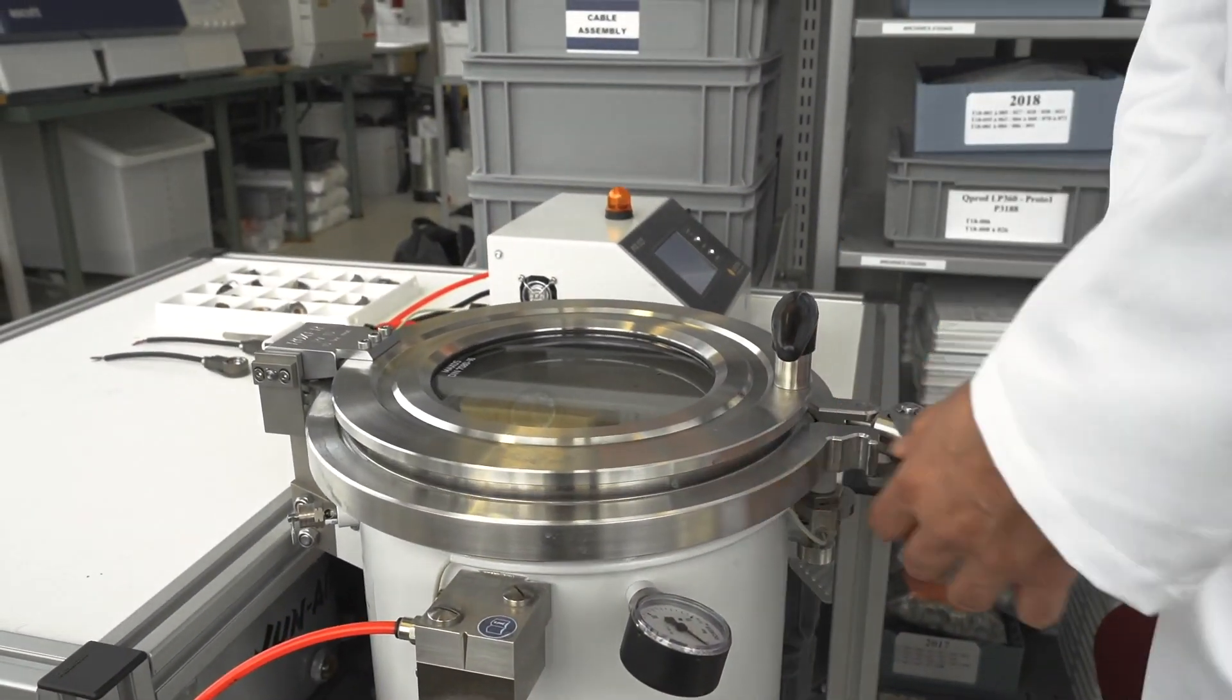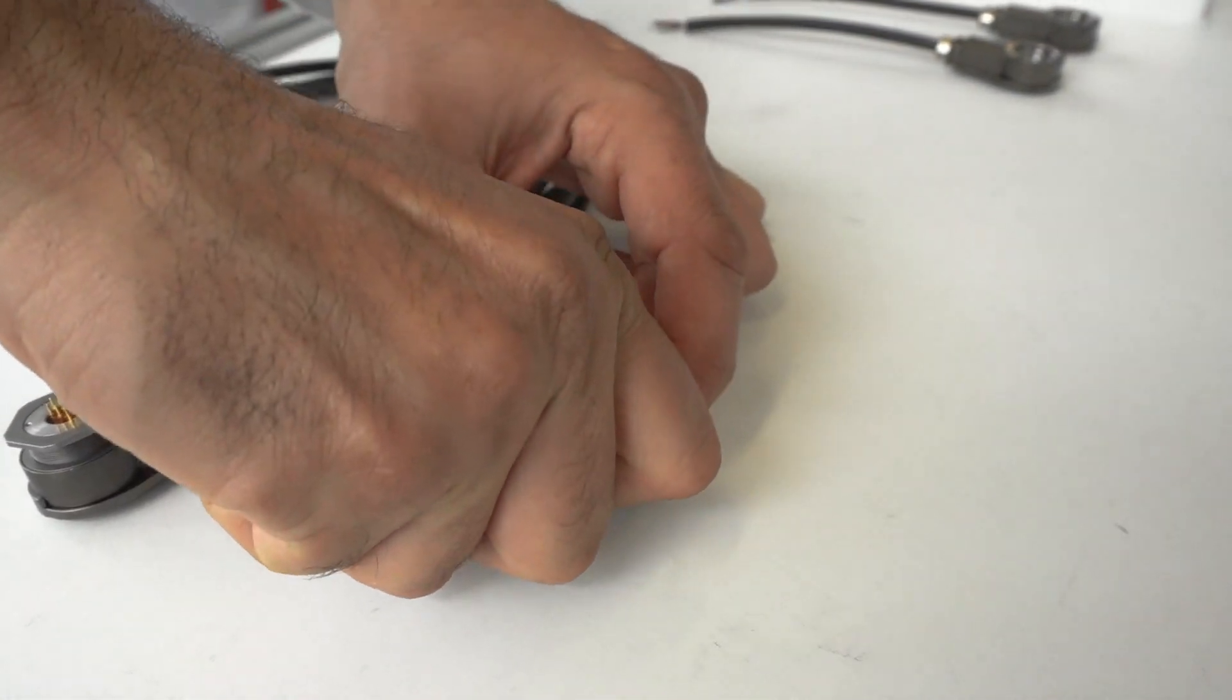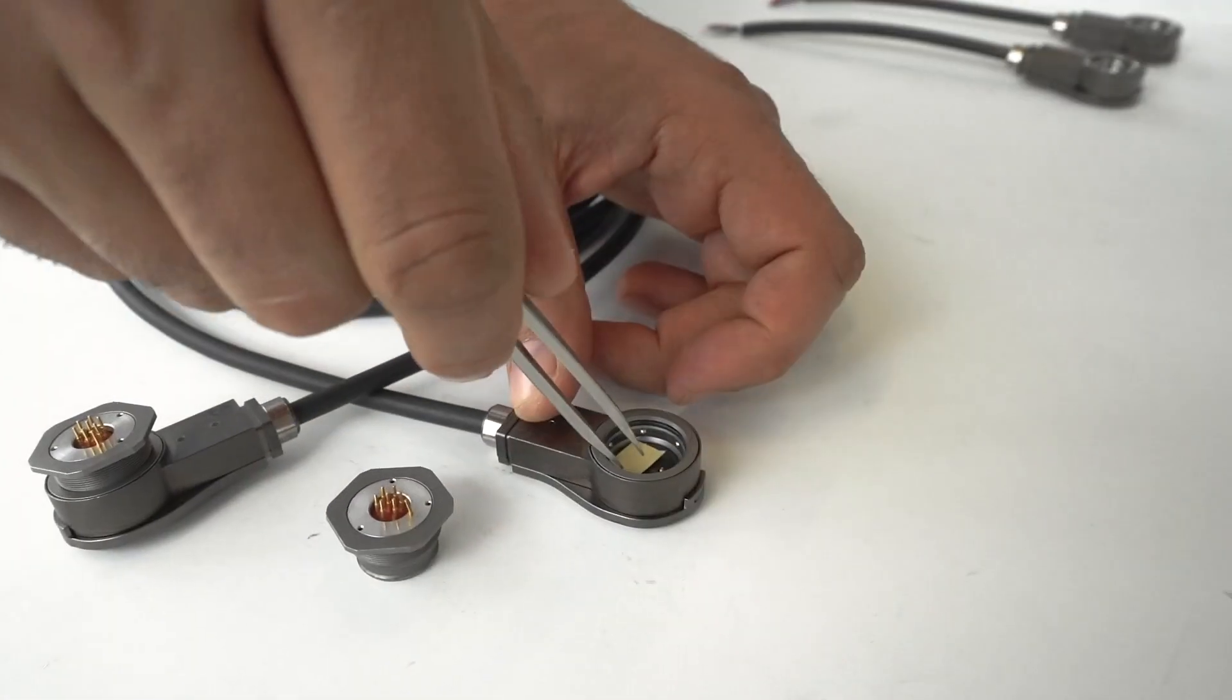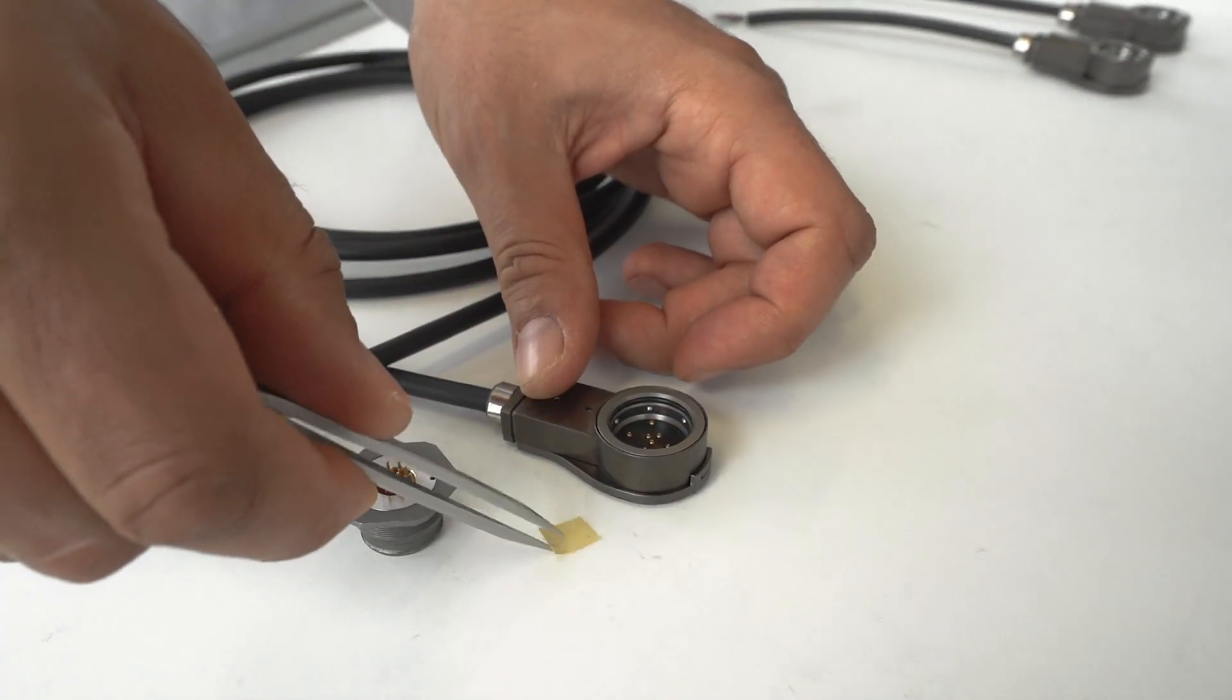After 24 hours of continuous immersion, the connectors are removed from the pressure vessel and unmated. No color change can be seen on the pH indicator paper, which indicates that no water has penetrated the connectors housing.